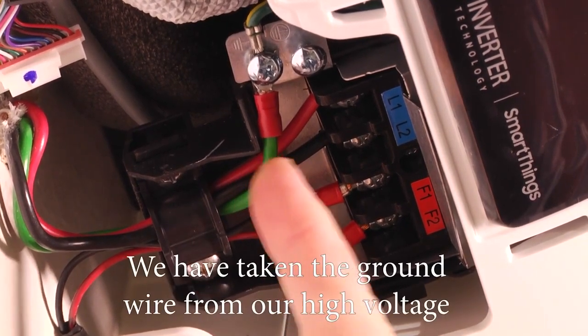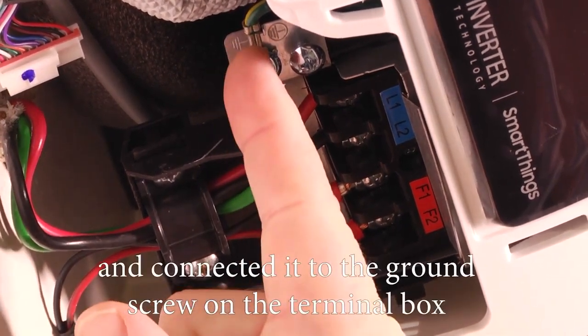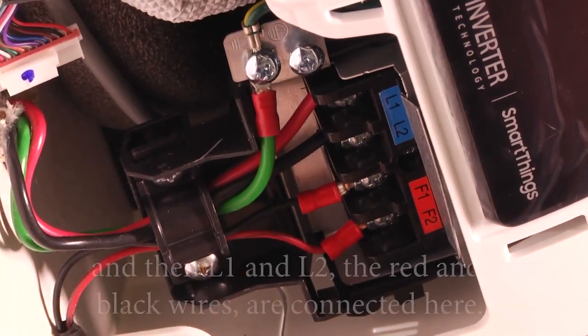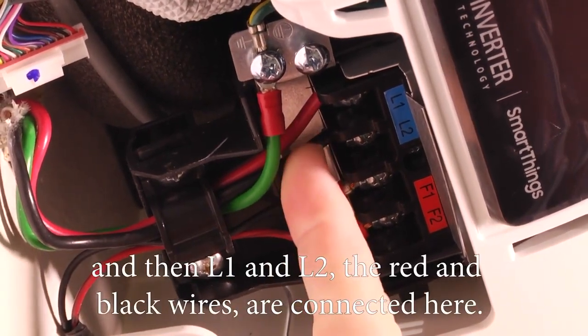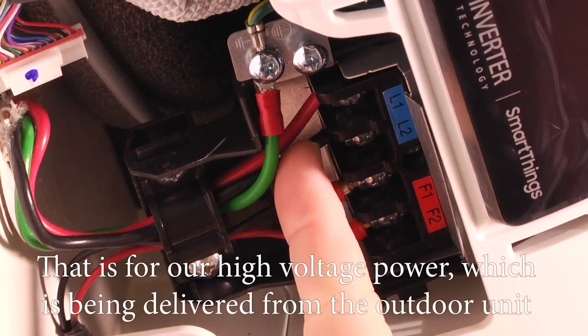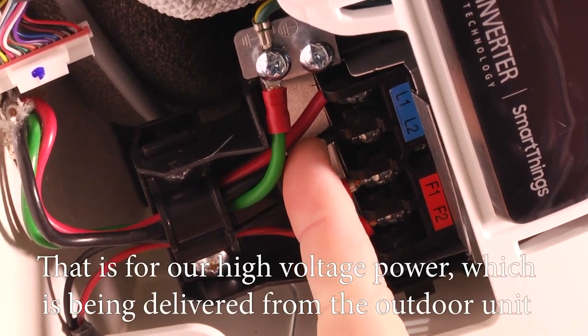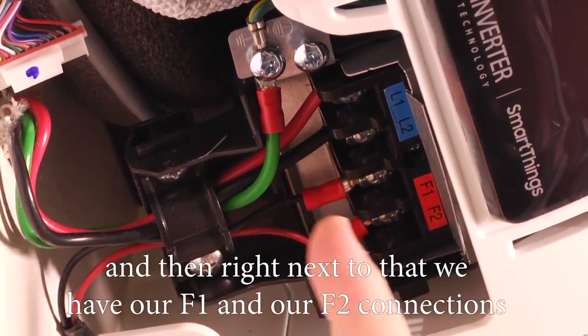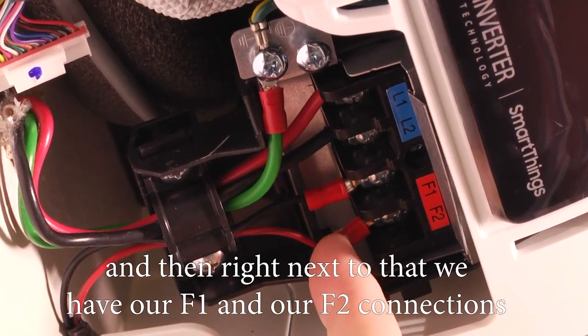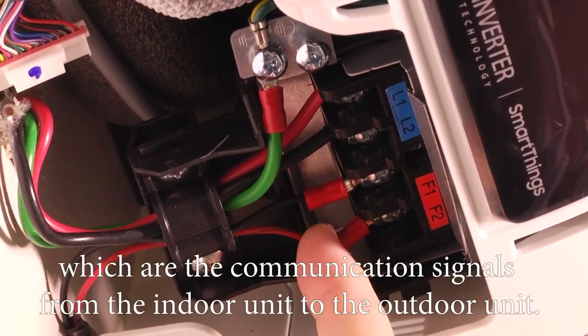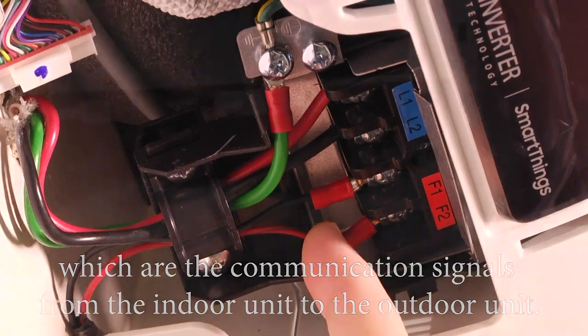We've taken the ground wire from our high voltage and connected it to the ground screw on the terminal box. And then L1 and L2, the red and black wires, are connected here. And that's for our high voltage power, which is being delivered from the outdoor unit. And then right next to that we have our F1 and our F2 connections, which are the communication signals from the indoor unit to the outdoor unit.